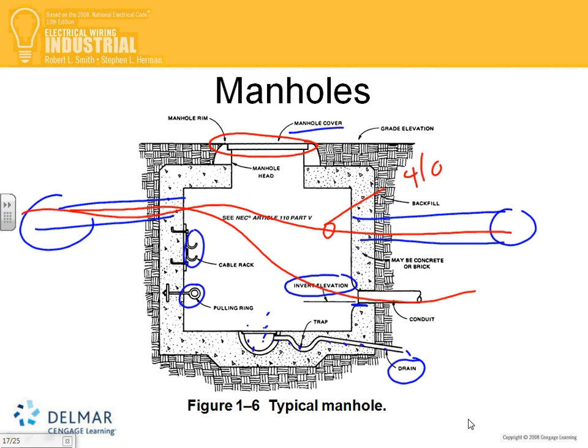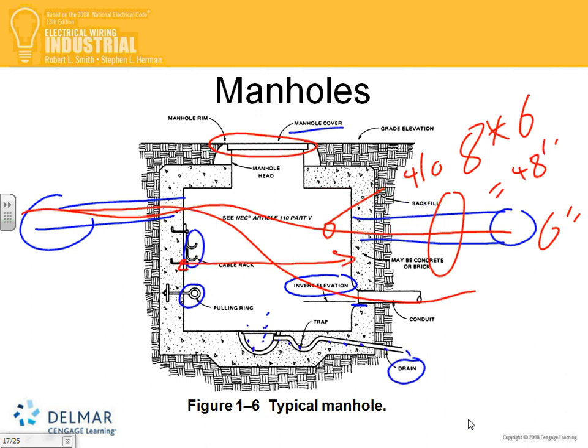But if you have just a manhole, guys, like this, just to pull cables in it, no equipment, no transformers, the only thing you need to pay attention to, if I want to size this manhole, Spencer, is that this is a pull box, exactly the rules of a pull box. This is a straight pull, 8 times. Suppose this was 6 inches, 6 times 8 equals 48 inches. So the distance from here to here, you need a minimum of 48 inches. That's one size. 48 inches minimum. I'm saying minimum. Drainage and the whole big spiel.